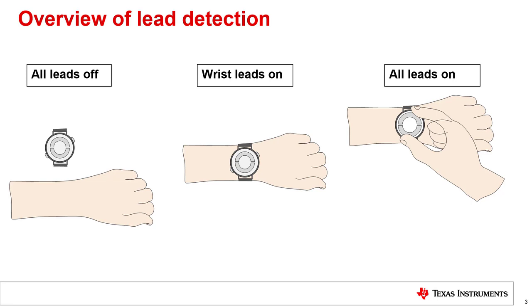As you can see from the illustrations, there are three possible conditions of connection to the electrodes. When the watch is off the wrist, none of the electrodes are in contact with the user — we call this the all-leads-off configuration. When the user wears the watch on the wrist, the bottom two electrodes make contact with the user — we call this the wrist-leads-on configuration. When the user touches the top electrode, all three electrodes make contact — we call this the all-leads-on configuration, in which the ECG signal can be acquired.